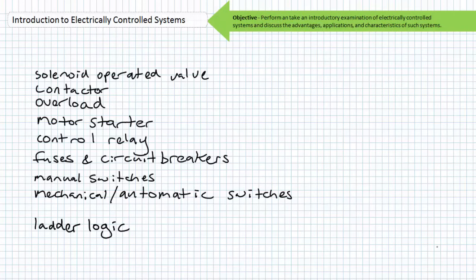The first part of the electrically controlled systems playlist is this lecture, which serves as the briefest of brief introductions to the topic. The next several lectures introduce key cast members of the electrically controlled systems family, principally the solenoid-operated valve, the principal interaction point between the electrical pilot and primary hydraulic aspects of an electrically controlled hydraulic system, the contactor, the principal interaction point between the pilot and primary electrical aspects of an electrically controlled system using motors, the overload, a means of protecting a motor from sustained overload conditions, the motor starter, being a combination of a contactor and overload, serving as a means of simultaneously starting and stopping a motor and protecting it from sustained overload conditions. The control relay, the principal logical element internal to an electrically controlled system.